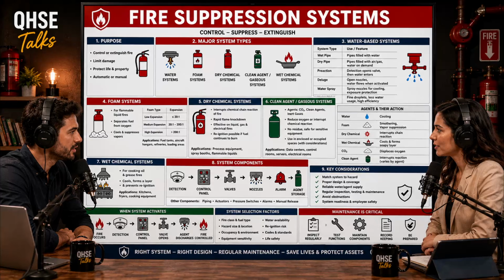What about dry chemical systems? Where do they fit in? Dry chemical systems utilize very fine pressurized powders. They knock down Class B and C fires incredibly fast by smothering, cooling, and acting as a physical shield between the liquid fuel and the radiant heat of the flames. But they must make a massive mess, right? An incredible pervasive mess. The fine powder gets into every crack, and many are highly corrosive to metals. You would never intentionally use a dry chemical system on sensitive electronics.